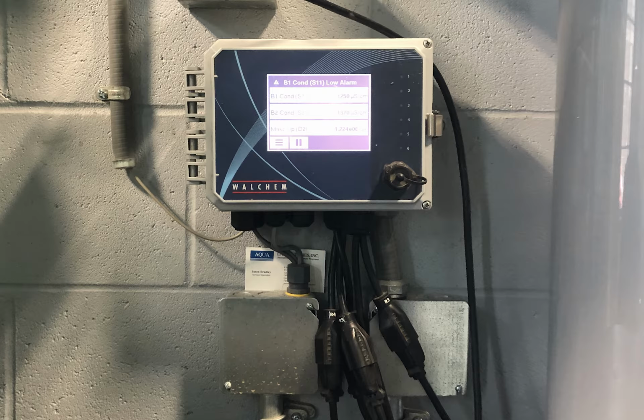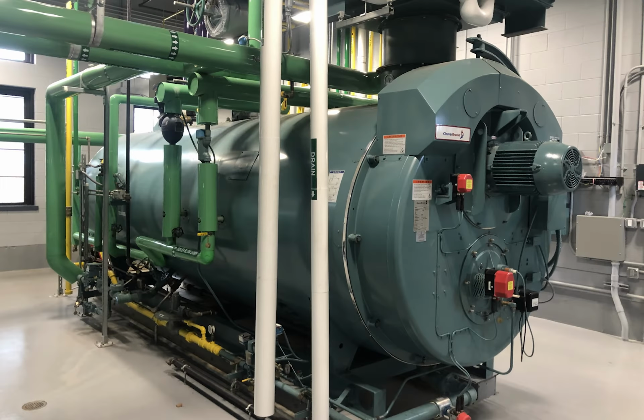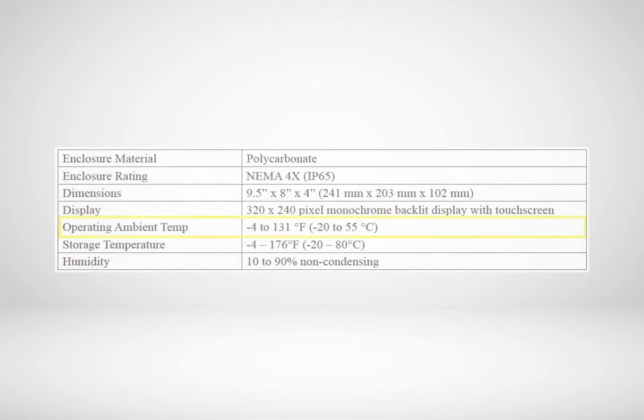It is very important when setting up a boiler controller in the boiler room that the ambient temperatures in the boiler room do not exceed that recommended by the controller manufacturer. This is usually somewhere in between -4 and 125 degrees Fahrenheit.